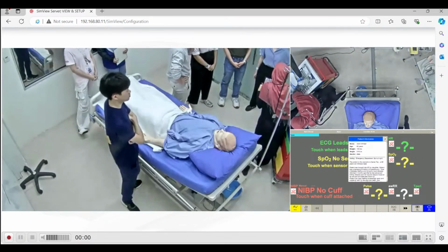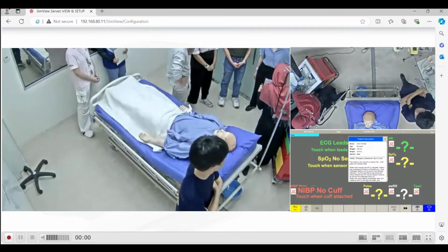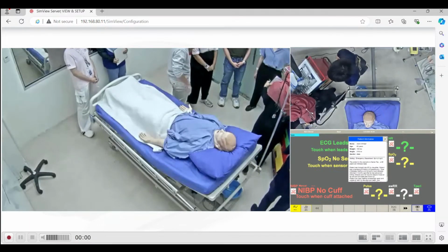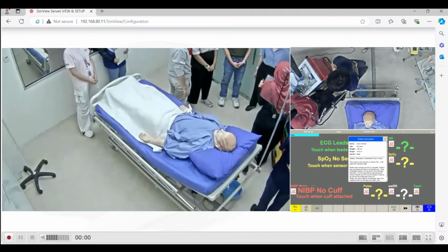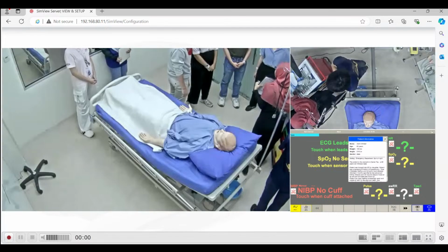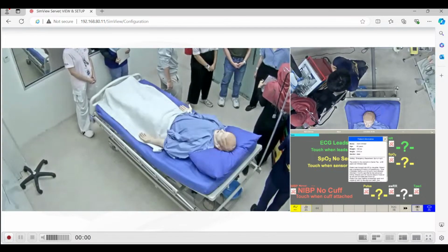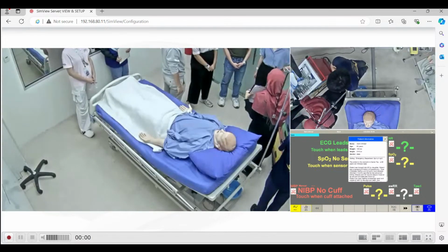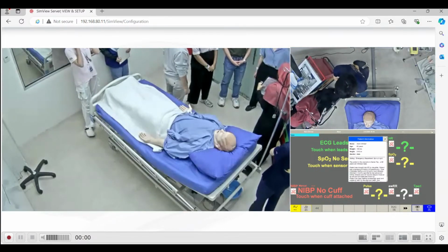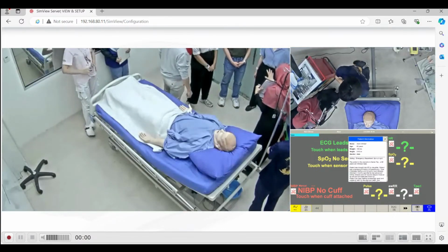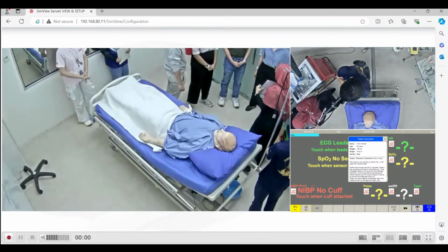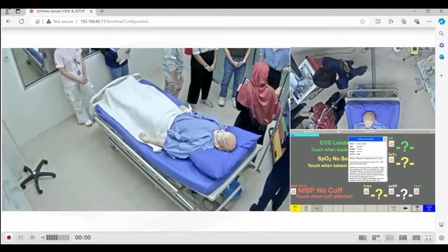So basically you just need to do this one and this one, potentially this one or this one, but to deliver a shock you need to press both pedals on this one. Is that okay? Alright. So remember, if Sean switches it off, it means that the joules is too high and he will sort it out. But actually I want you all to do all this because in real life these are the things that will take up your task, okay?